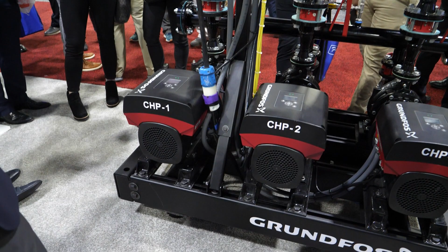Absolutely. Basically what we're looking at is a primary secondary system done a little bit differently, to ultimately optimize the chill water system. So here we have a typical 3-pump, or triplex, primary pump set. These are Grundfos pumps, the MBS model. They're split coupled, no alignment, silicon carbide seals, so a very durable, robust design that's going to last a lot longer than a traditional end suction type pump in this application.